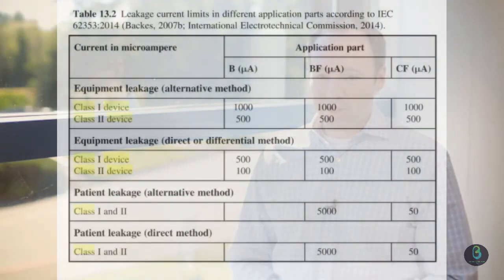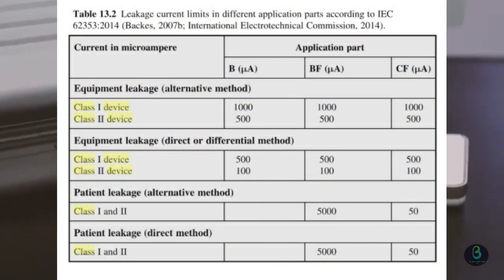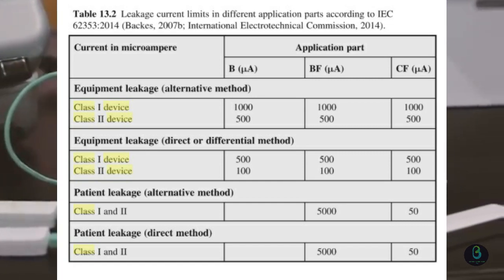And leakage measurement limits have been developed for equipment types and measurements. They include NC, normal conditions, and SFC, single fault conditions.